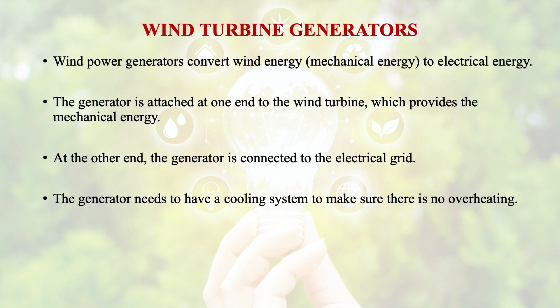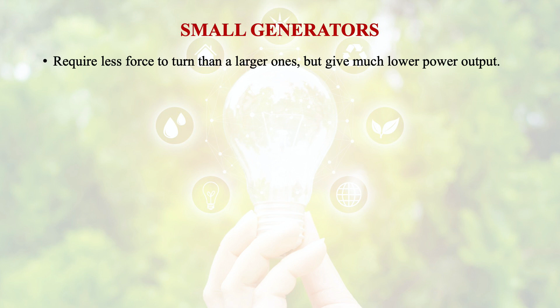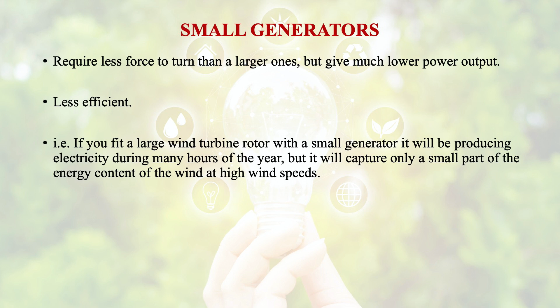Generally, two kinds of generators are there, the small generators and large generators, depending upon the power requirement or the application where we are going to install this power. Generally, the small generators require less force to turn than larger ones, but they give much lower power output. They are less efficient. That is, if we fit a large wind turbine rotor with a small generator, it will produce electricity during many hours of the year, but it will capture only a small part of the energy content of the wind at high wind speeds.